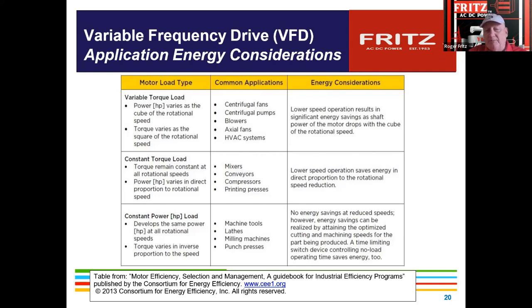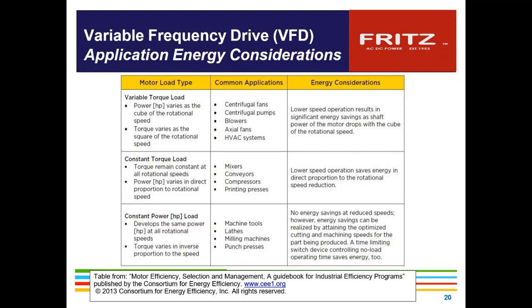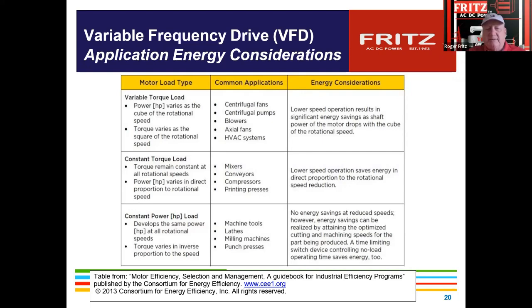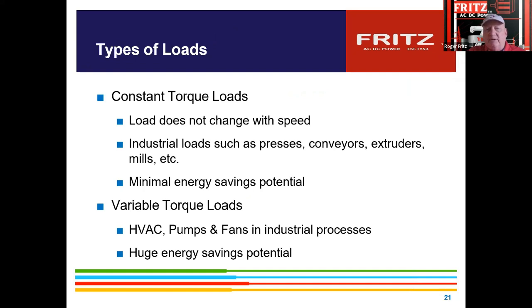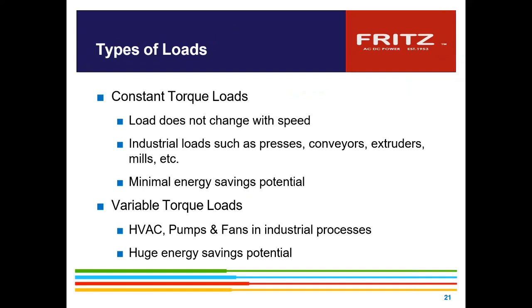But with constant torque loads, by lowering the speed, you do get more of a linear savings. And then compressors, it depends on the type of compression it is. Conveyors, it's whether or not you can really slow the conveyor down, let's say it's in a rock plant or whatever. Printing presses, again, the same thing. There are vacuum pumps and things in there that you need to take a look at. Mixers, we've done a lot of work for various places that had mixing requirements. Again, back to what a constant torque load is, variable.